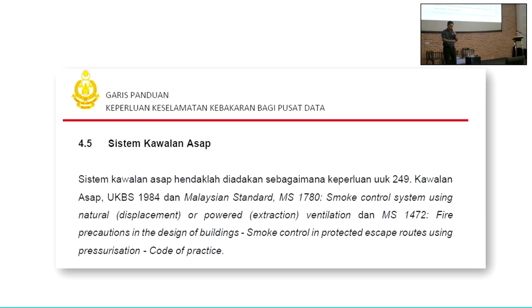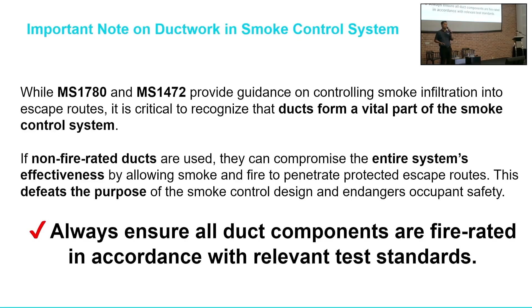So now it's back to us whether what I said today makes sense or not. You have very good standards, but what if the duct collapses? Then your smoke will never get out of the building, at the end of the day. So importantly, for you architects to consider - all your duct components should be fire rated. You cannot just have a blanket statement saying you meet the airflow requirements, because if the components are not made out of fire rated systems, then it defeats the purpose of the entire exercise.